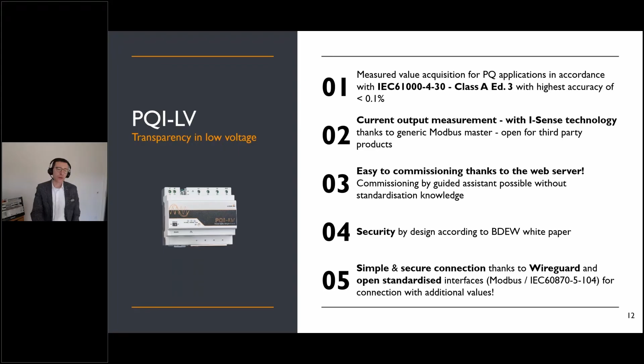One more thing, the second point: you have the opportunity to extend the measurement technology to 2 until 20 kilohertz as an option. So if you decide now you don't need that, install the device like it is. It's a cheap device for a power quality device with class A. And if you need the supraharmonic measurement in the future, you can do that by adding an option on the device itself. This is good news, I think, because why?